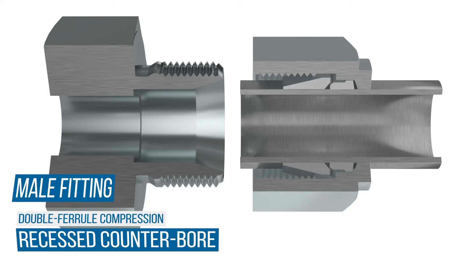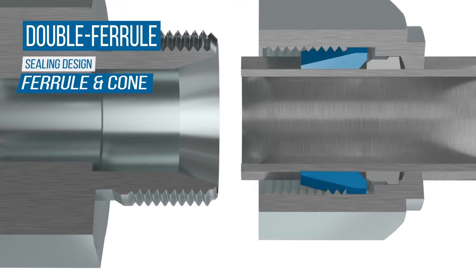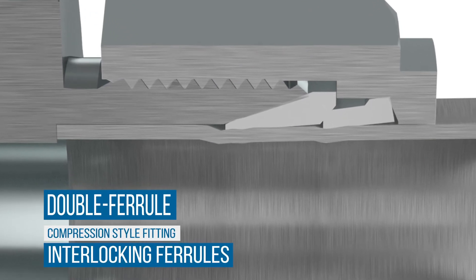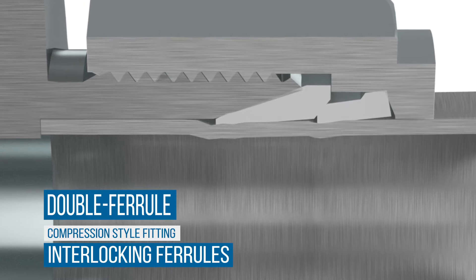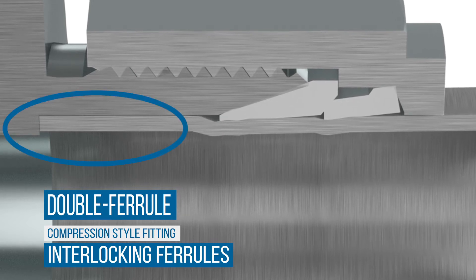The male end of a double ferrule instrumentation fitting has a recessed counterbore, which matches the tube OD being used, plus an inner bore. The seal is made between the front ferrule and the cone. The tubing is held in place by the swaging action caused by the tightening of the nut, which forces the front and back ferrules to bite into the tubing, firmly holding it in place. The ferrule coins and compresses into the tube to provide a tight grip on the tube surface, allowing for the use of unflared tubing with these connectors.